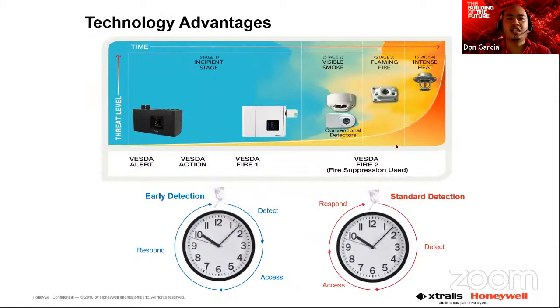Another technology advantage, si VESDA po, it has 4 levels of alarm sensitivity or alarm threshold: VESDA alert, action, fire 1, and fire 2. Ang alarm threshold na ito, depende sa smoke presence sa loob ng VESDA detector.